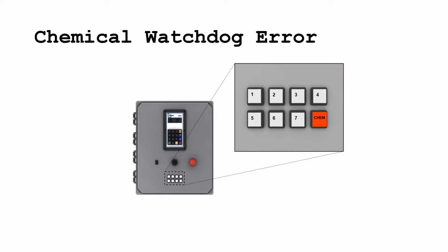If this is a catalyst system error, the chem button should be flashing. If a machine button is flashing, then it is a machine error where the machine did not answer the chemical request. If multiple buttons are flashing, clear the machine errors first. Make sure to press the flashing button of the machine or chem system you want to clear before you begin.